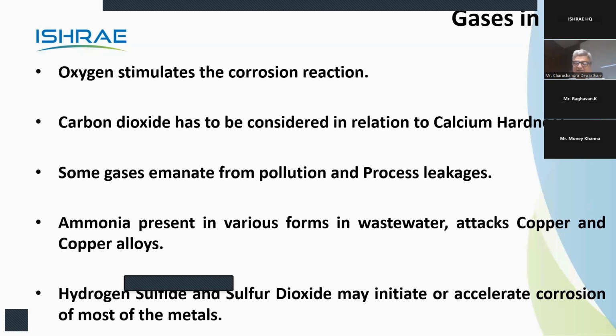Now you'll understand that split air conditioner condensers are normally kept outside. In our MIDC, Maharashtra Industrial Development Corporation, we have chemical plants and mechanical plants. In the case of chemical plants, the split AC condensers kept outside in the fresh air corrode very fast. I've seen people changing their condenser every 6 months. That is corrosion, and it is because of SO2.